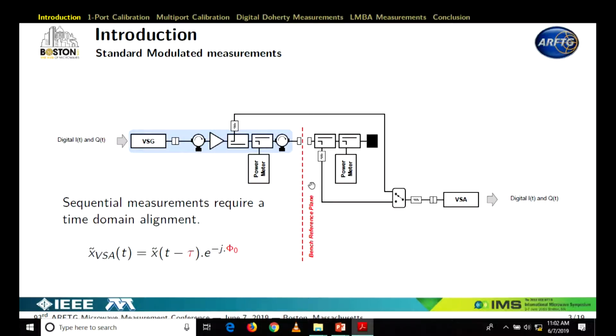And if we want to calibrate the source, basically the calibration of the source, not calibration in terms of measurement accuracy, we will measure with the receiver just in order to know approximately the level we want to apply in terms of the source. So we need to know, according to the calibration between the instrument here and the DUT, what is the power offset between the command and the DUT reference plane over there. I will talk about that during the whole presentation.